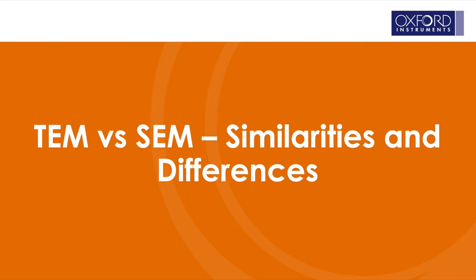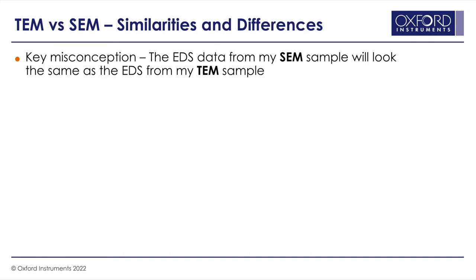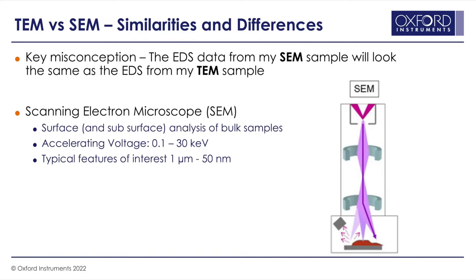TEM versus SEM — what's the same, what's different, what does it mean? A key misconception is that EDS data from an SEM will look very similar to EDS data from a TEM, though the technique is the same, this typically isn't true. A scanning electron microscope is a surface or subsurface analysis technique that looks at bulk samples, with an accelerating voltage of about 0.1 to 30 kV. The features of interest are probably going to be in the micron range, down to the nanoscale, but not typically anything smaller than 50 nanometers.